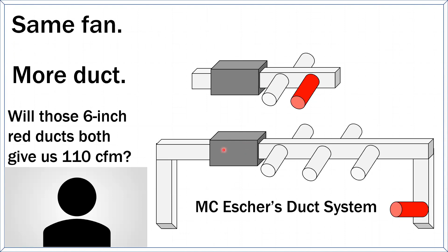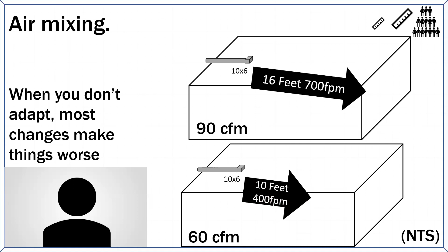The other thing that we lose when we have a bigger volume and lower airflow is air mixing. Right. And so back when we were putting 90 CFM in this room, we'd throw the air 16 feet, right? It'd be 700 feet per minute. Now, if I'm going to use the same 10x6 grill, but I'm only going to have 60 CFM coming out of it because, you know, that's 10x6. That's what goes in a bedroom. Now I'm only throwing the air 10 feet. Doesn't go as far. It doesn't get to the outside perimeter of the building. Less important that it does, by the way. But this 400 feet per minute's a problem. That seriously causes air stagnation. So what we actually need to do in this space is put an 8x4 in there. Well, they don't sell that in the supply house.